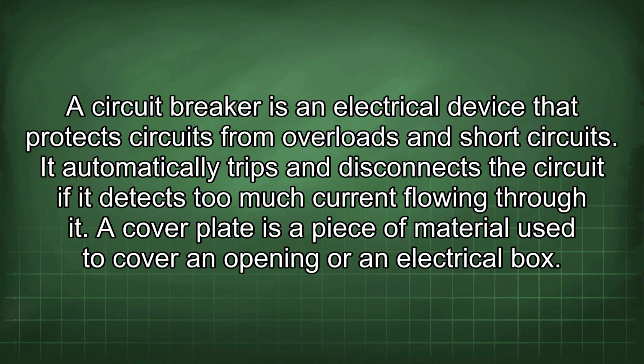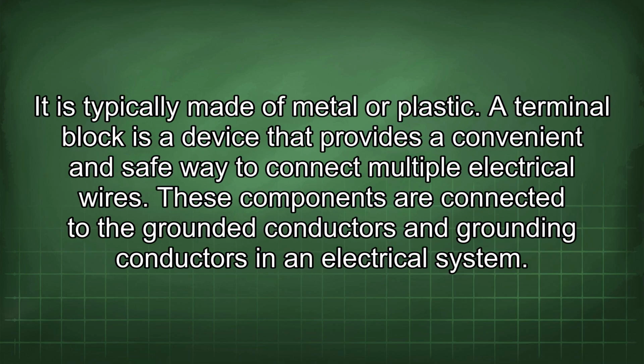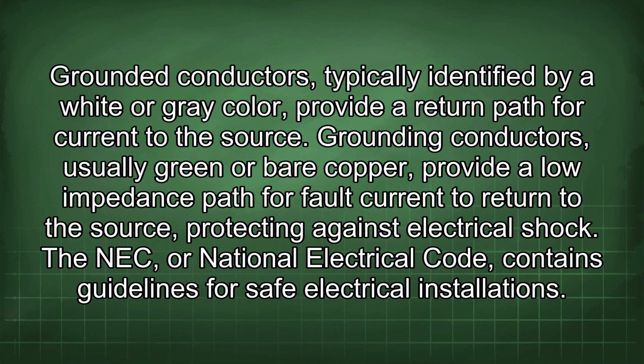A cover plate is a piece of material used to cover an opening or an electrical box. It is typically made of metal or plastic. A terminal block is a device that provides a convenient and safe way to connect multiple electrical wires. These components are connected to the grounded conductors and grounding conductors in an electrical system. Grounded conductors, typically identified by a white or gray color, provide a return path for current to the source. Grounding conductors, usually green or bare copper, provide a low impedance path for fault current to return to the source, protecting against electrical shock.